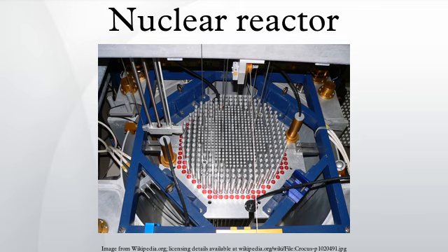At the end of the operating cycle, the fuel in some of the assemblies is spent, and is discharged and replaced with new fuel assemblies, although in practice it is the buildup of reaction poisons in nuclear fuel that determines the lifetime of nuclear fuel in a reactor. Long before all possible fission has taken place, the buildup of long-lived neutron-absorbing fission byproducts impedes the chain reaction. The fraction of the reactor's fuel core replaced during refueling is typically 1/4 for a boiling water reactor and 1/3 for a pressurized water reactor.